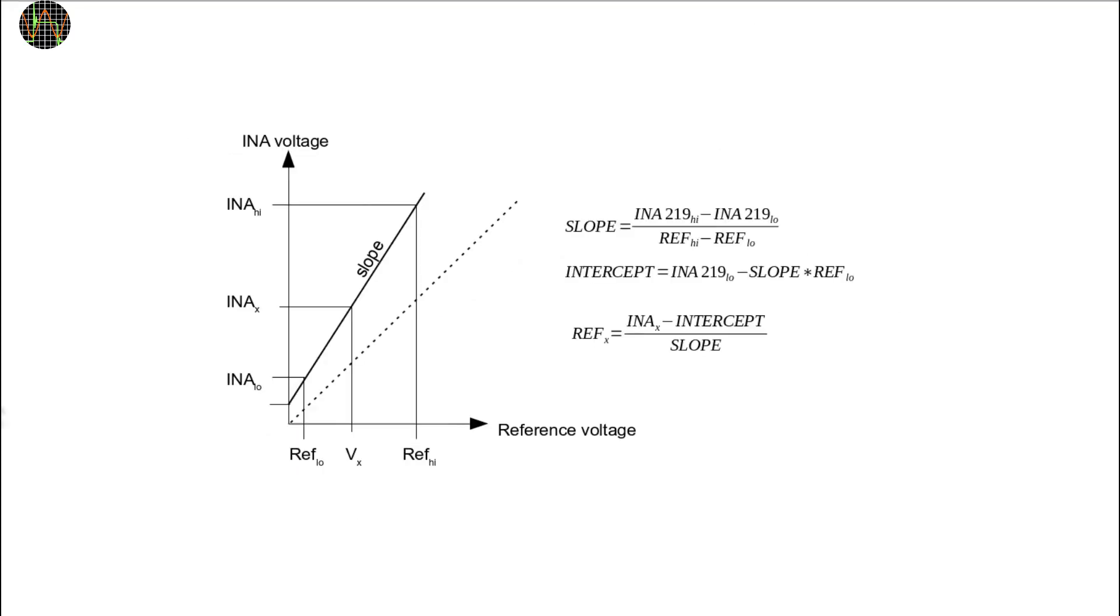Here is a brief recap of that method. We basically take two pairs of measurements, one on the INA219 chip in the Powermon and one by a reference DMM. One pair is for the low side of the range and one pair covers the high side.